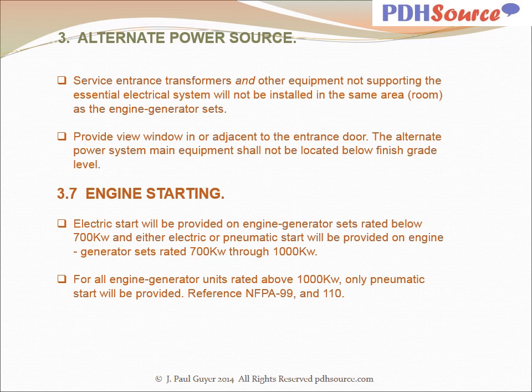Service entrance transformers and other equipment not supporting the essential electrical system will not be installed in the same area or room as the engine generator sets. Provide a view window in or adjacent to the entrance door. The alternate power system main equipment shall not be located below finish grade level.